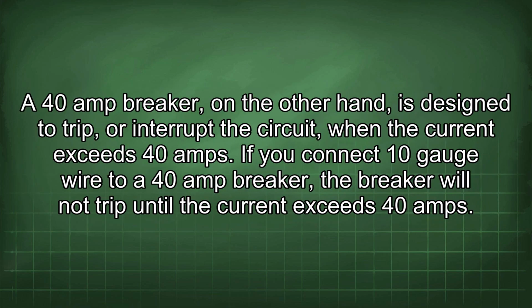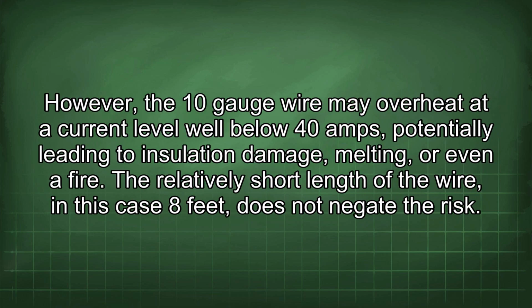A 40-amp breaker, on the other hand, is designed to trip or interrupt the circuit when the current exceeds 40 amps. If you connect 10-gauge wire to a 40-amp breaker, the breaker will not trip until the current exceeds 40 amps. However, the 10-gauge wire may overheat at a current level well below 40 amps, potentially leading to insulation damage, melting, or even a fire.